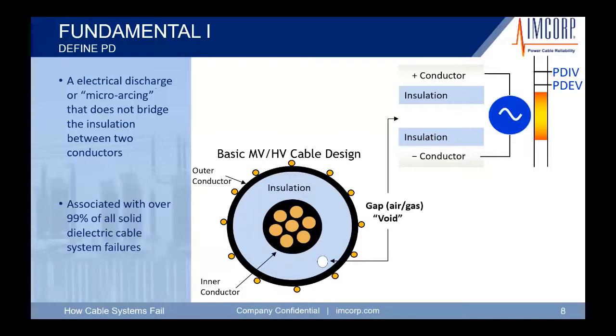And then we have our PDIV and PDEV. PDEV is partial discharge extinguishing voltage, when partial discharge does not grow. PDIV is a transient voltage. It's a level that's more than operating voltage that ignites the PD activity in the cable. So by looking at this, once we hit partial discharge inception voltage, we begin to see and fire off the partial discharge. Once we go below PDEV, it extinguishes itself. Now, as this begins to grow, this erosion process is happening. That carbon tree begins to grow. Once PDIV gets closer to operating voltage, we know that this excitement of partial discharge is going to be continuous, so it'll eventually break down this cable and cause a fault.